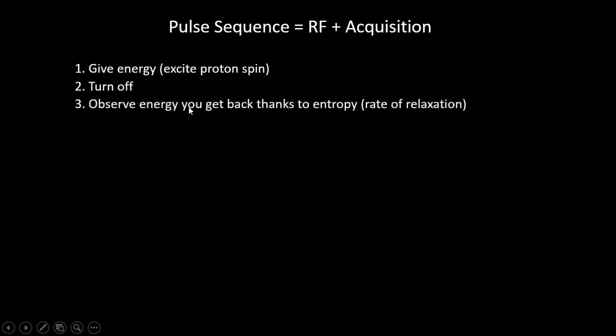What am I talking about when I say pulse sequence? An MRI sequence is basically a sequence of events that happens inside the MRI machine that gives you your image. Each pulse sequence consists of two basic components: your radio frequency component and your acquisition phase. First, we give energy to our system or tissue — we excite proton spins using radio frequency energy. Next, we turn off that source of energy, and finally we observe the energy we get back from that excited tissue due to relaxation of the proton spins back into alignment with the magnet. The differences in rates of relaxation of protons in different tissues give us our contrast.